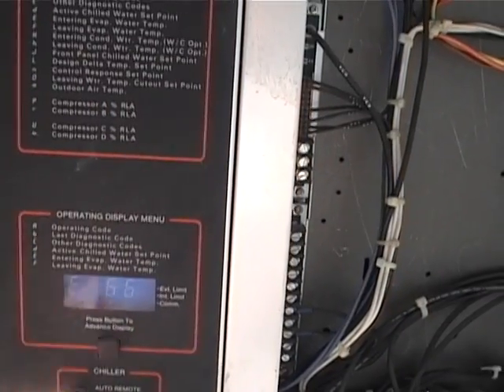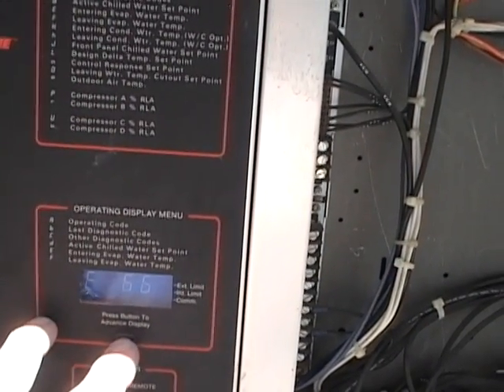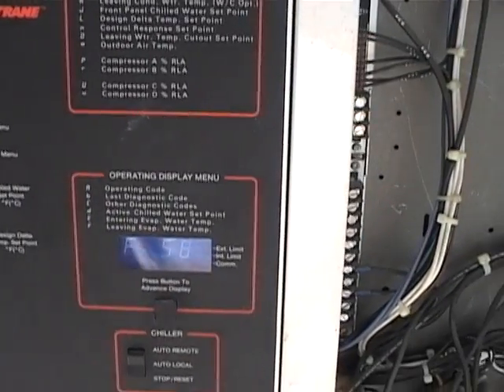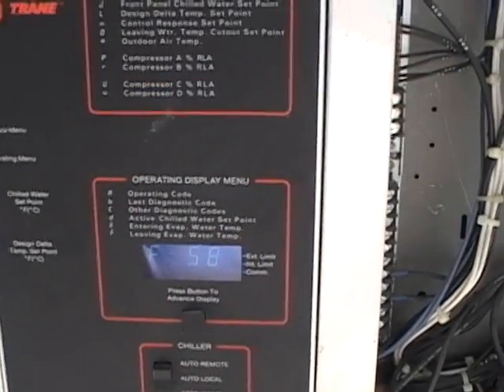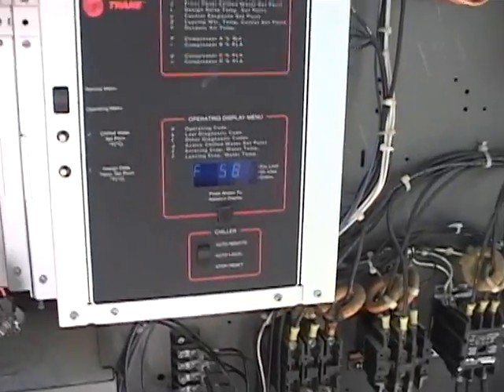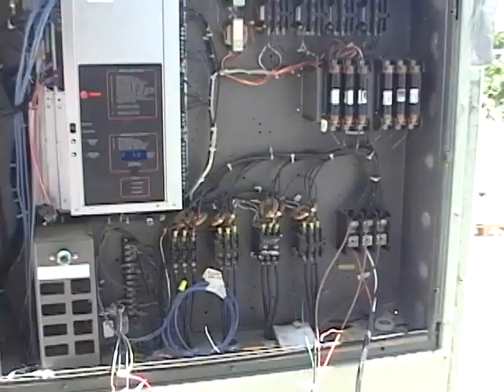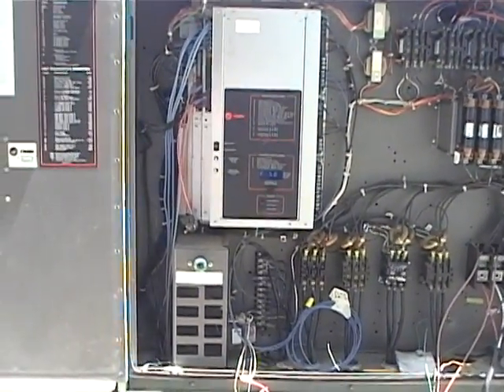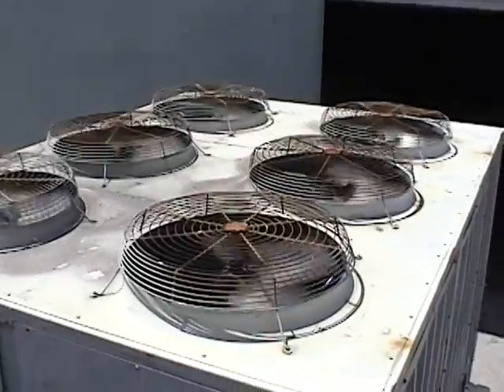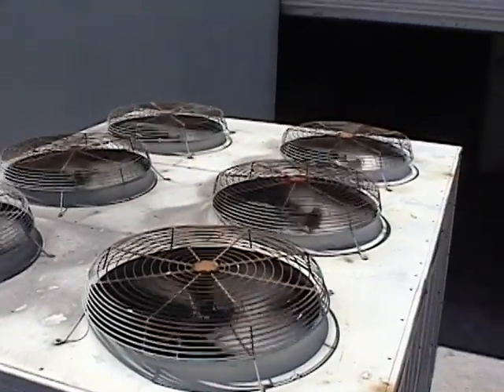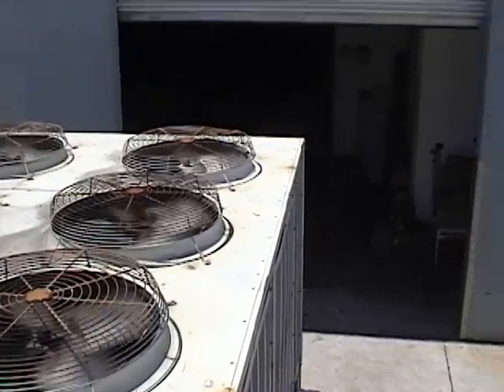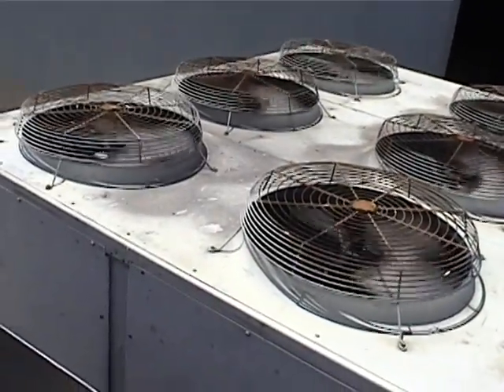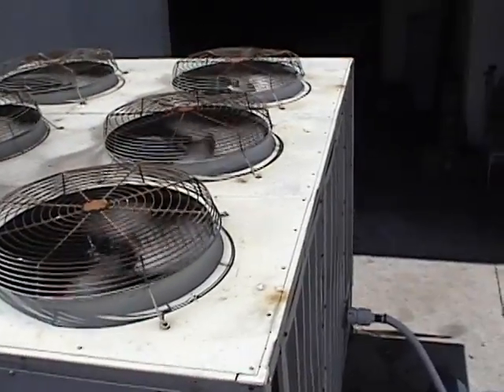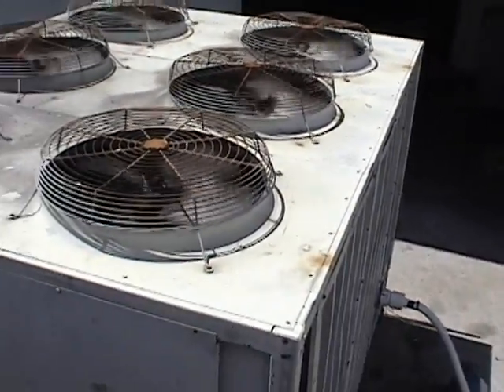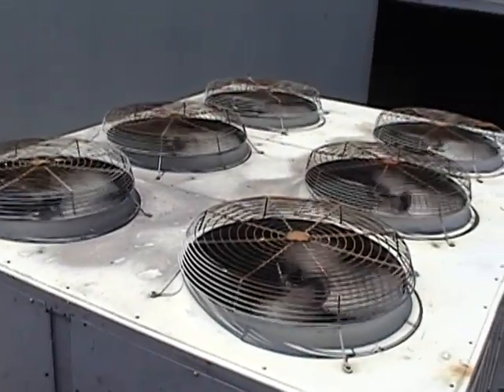67, 66 is now our incoming. This is now the temperature of the water coming from the aluminum holding tank. Entering the chiller now is 66. And our water leaving the chiller is now 58. So we're doing very well over here. She's coming way down in temperature extremely fast. But it is a big chiller, 55 tons. Notice that we have all 6 fans turning. All 6 fans are blowing and pulling air through the heat exchangers. They're all running. Every one of them runs well.